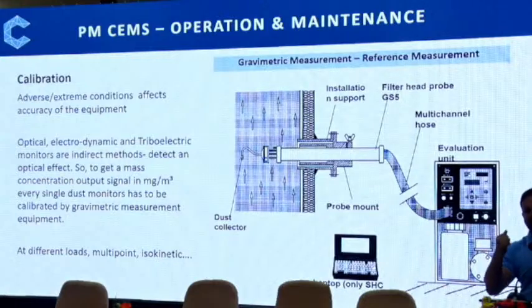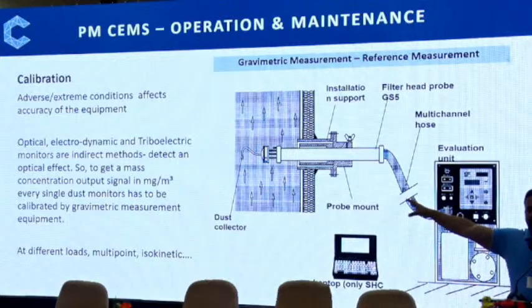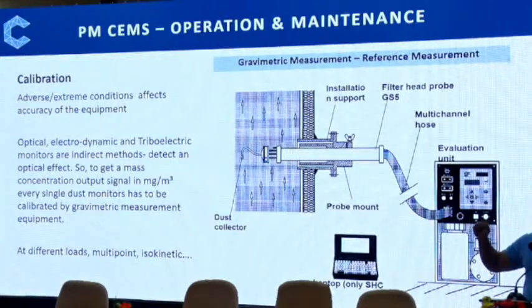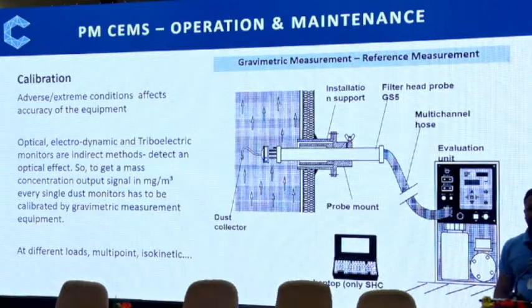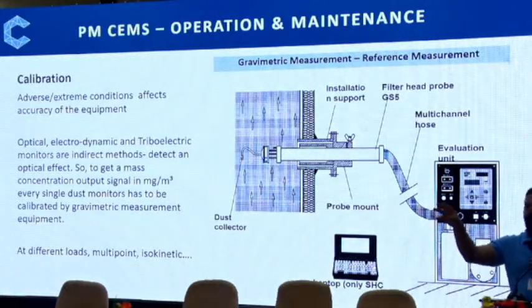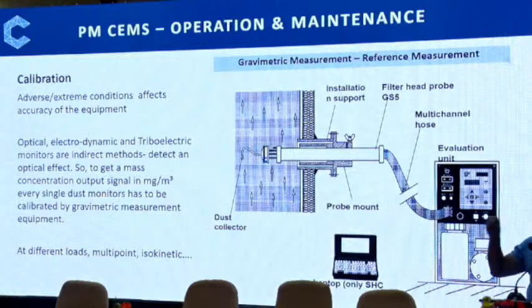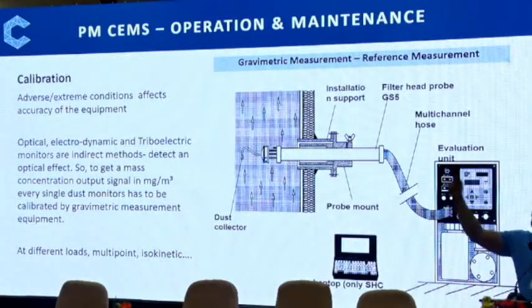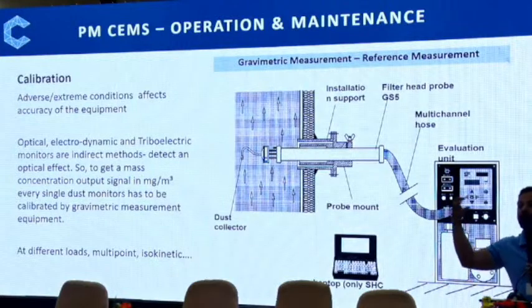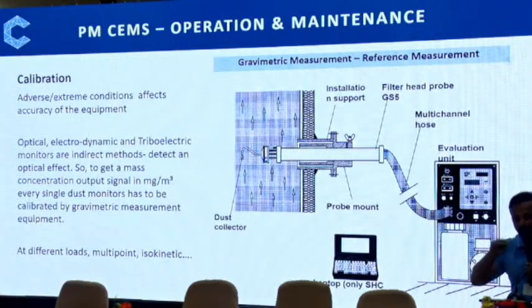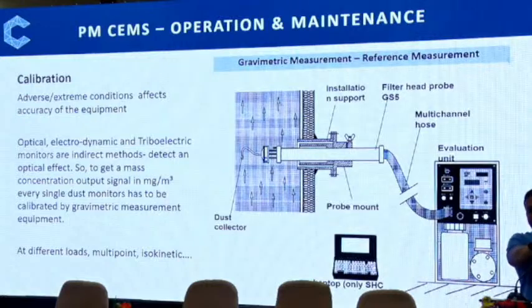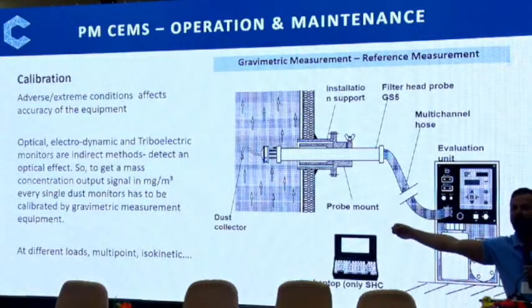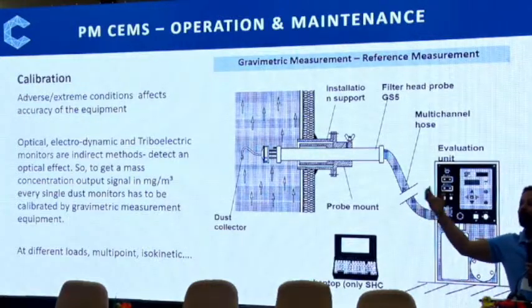That is why we do the calibration. So in calibration, what do we do? We have a monitor installed, CEMS installed, and it is giving you a reading. At the same time, we do the gravimetric monitoring. Gravimetric means the manual monitoring we do. So for that particular condition, you have a reading in CEMS, milliampere or electron volt, depending upon the technology. And at the same time, you know how much dust you have got, in milligram per meter cube or milligram per normal meter cube. So you know this much milliampere or this much CEMS reading is equivalent to this much milligram per normal meter cube. That is the calibration.